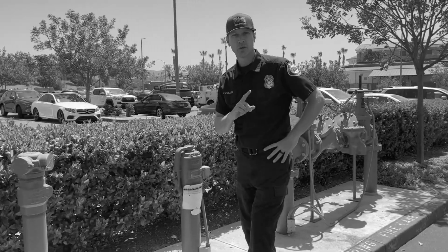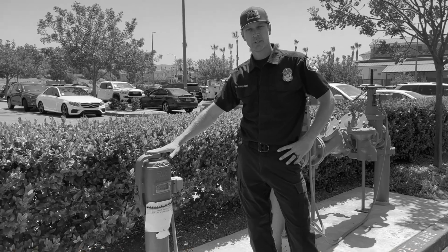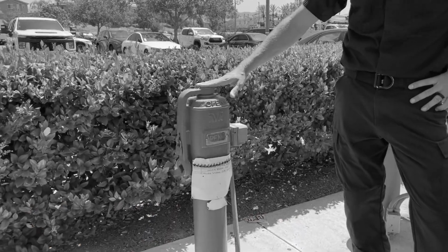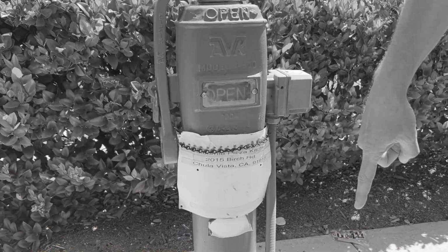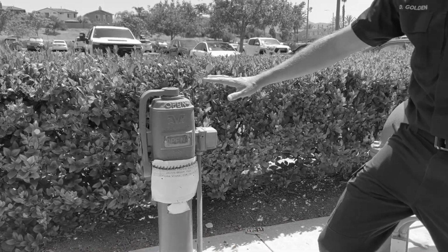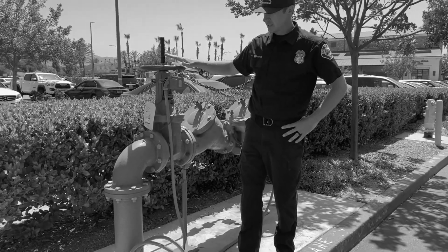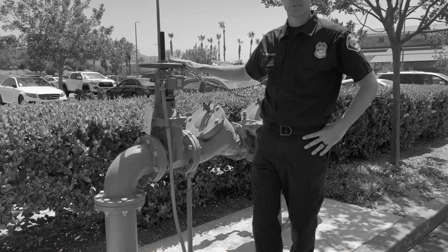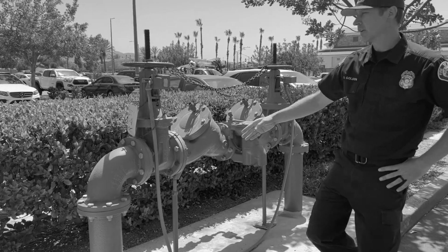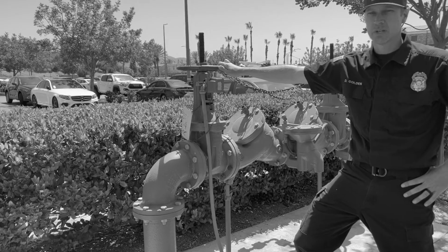If you don't have a control valve on a sprinkler riser, you're going to want to locate your yard PIV or exterior PIV. This is a control valve underground, or a device that goes to the underground control valve. If you don't have a PIV, your next option is a backflow prevention device which has 2 control valves on it. Either one of them will shut the system off. You don't have to shut both of them off.